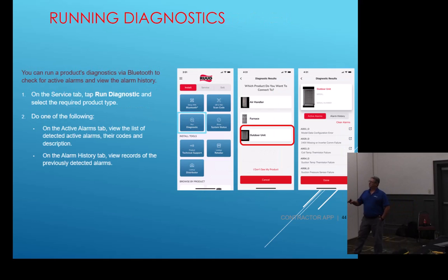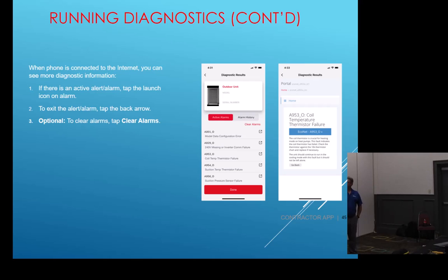If you have just the guest account, this is what you're going to get. Okay? If you have the login feature, then you can click on this tab and you get this to come up. Now it's going to go through and tell you the coil thermistor is a crucial part for heating and cooling. The fault indicates the coil thermistor has failed. Check the thermistor on the 10K ohm chart. Replace if necessary. That's a very basic and short one.